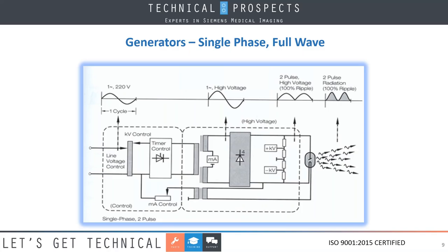Notice though, also you see a plus and minus KV in the circuit there, because when we talk KV, we're talking potential across the tube. For example, if I'm making an 80 KV X-ray, you will note that the positive side will be at 40, the negative side will be at minus 40. However, the full potential across the tube is 80 KV. The MA control also ties into this, and you can see goes into the cathode side of the X-ray tube, which is where our filament is, and this all gets tied together.